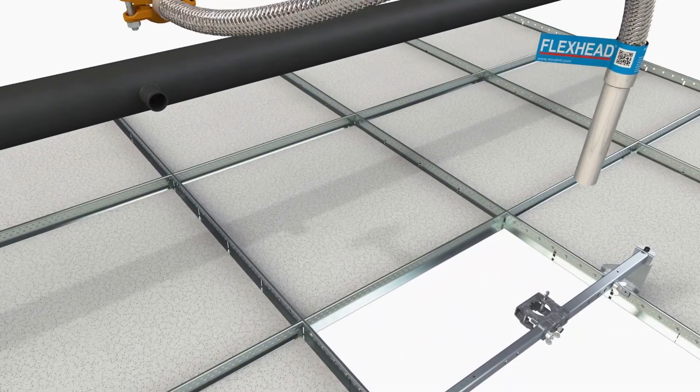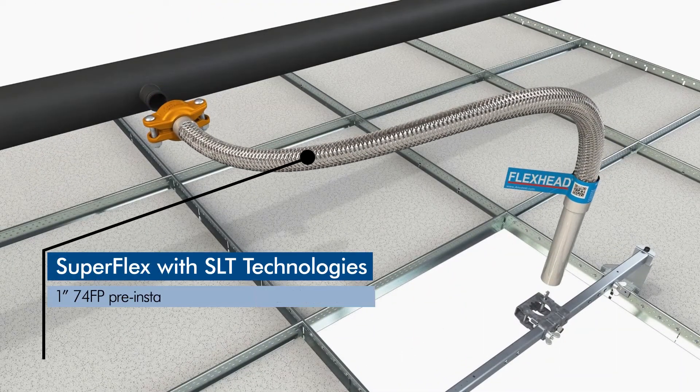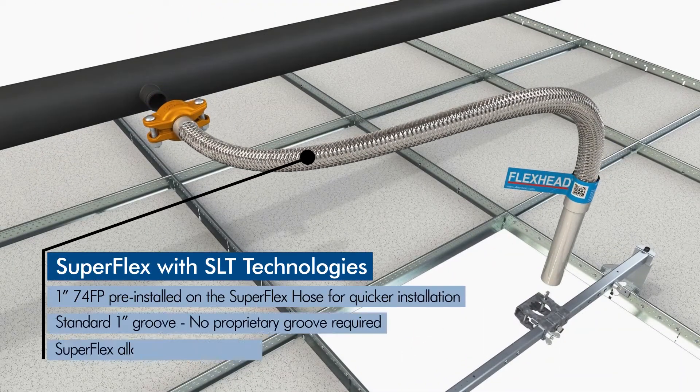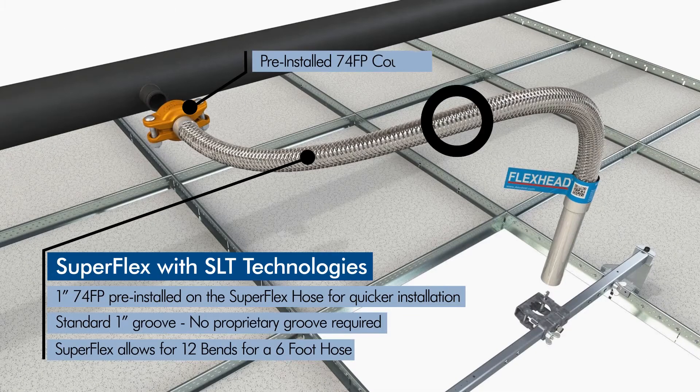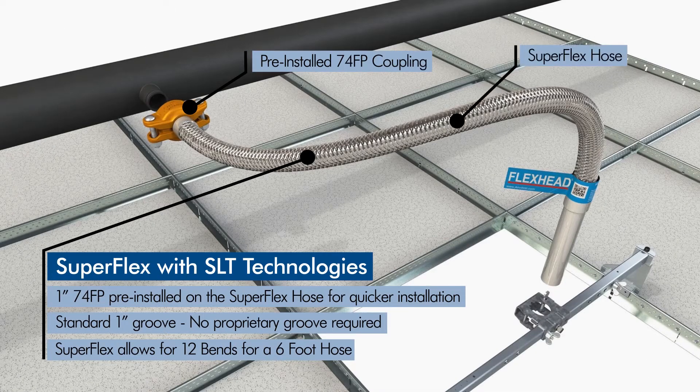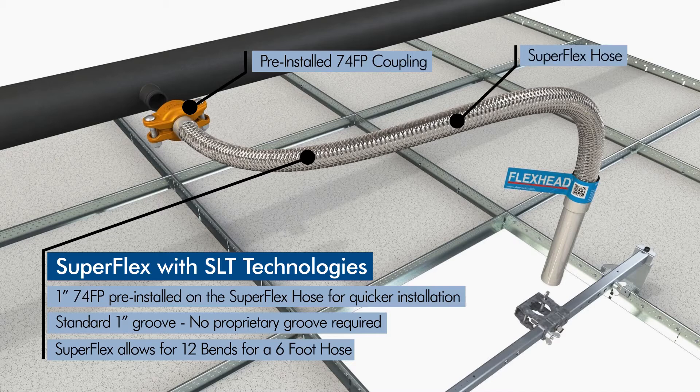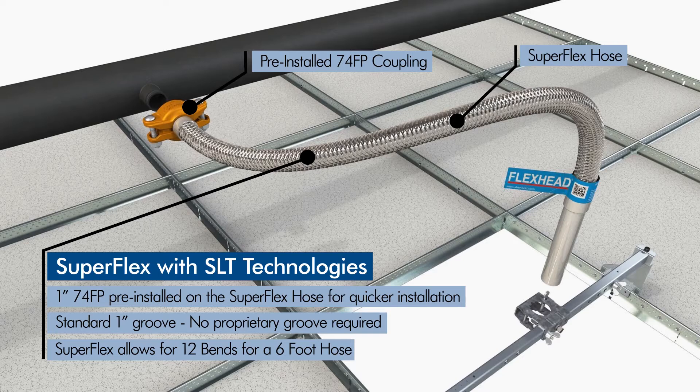Combining the SuperFlex with SLT Technology and the SlideLok 74FP Coupling creates a fast, error-free installation. All SLT SuperFlex Hoses can be used with national standard 1-inch groove components. No proprietary groove required.